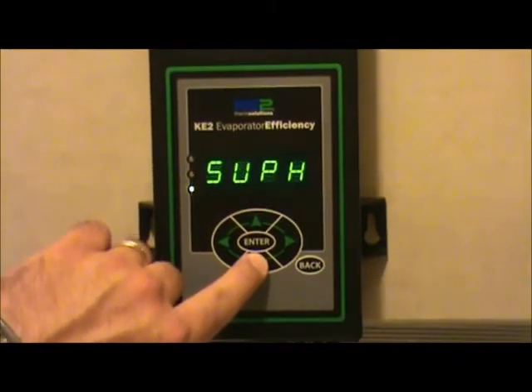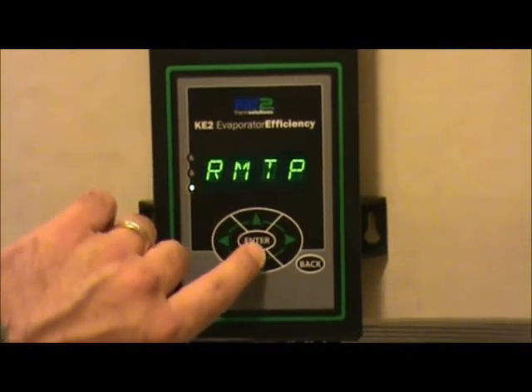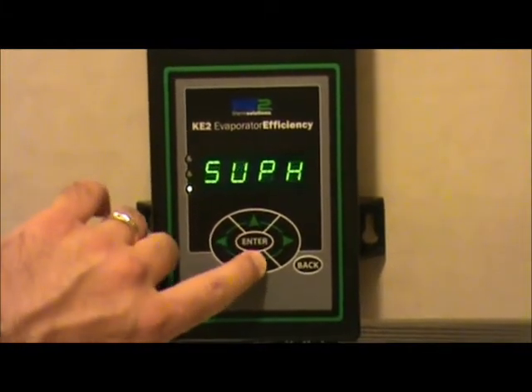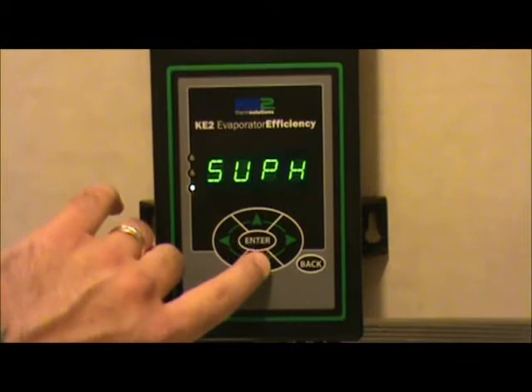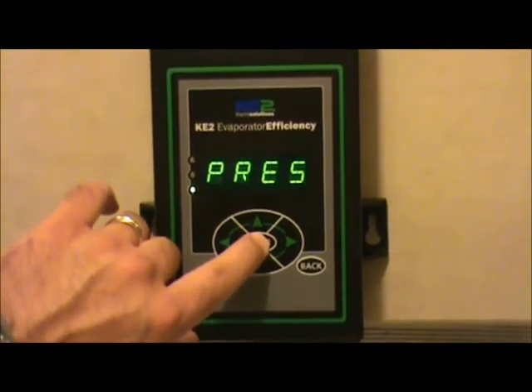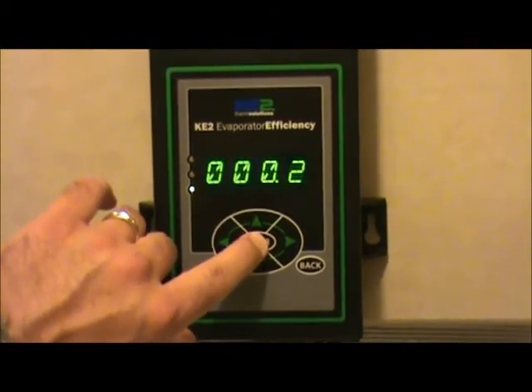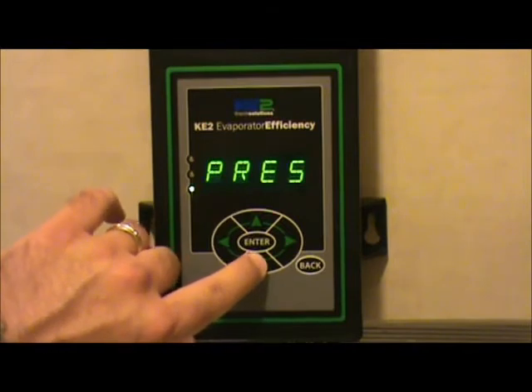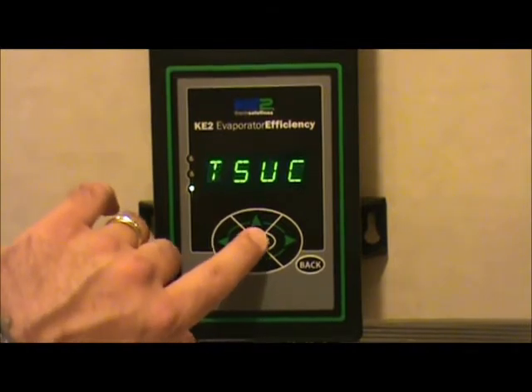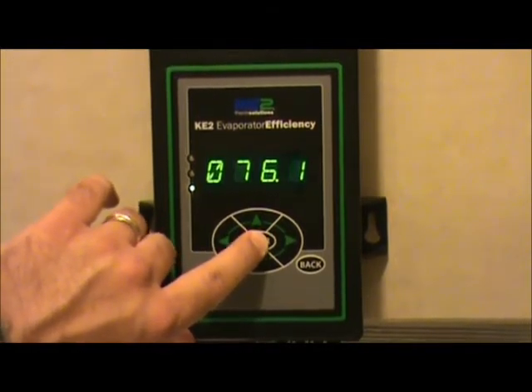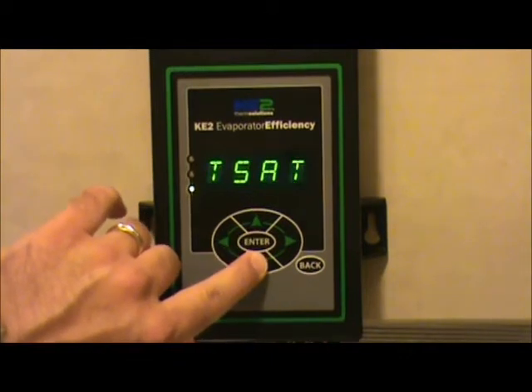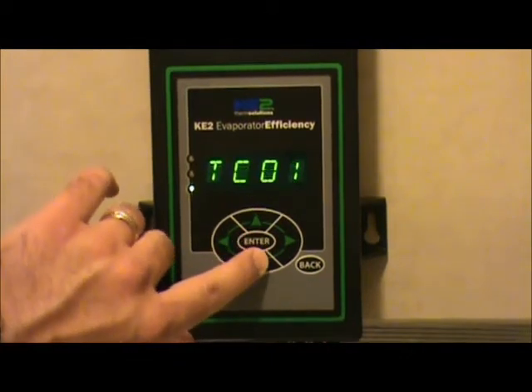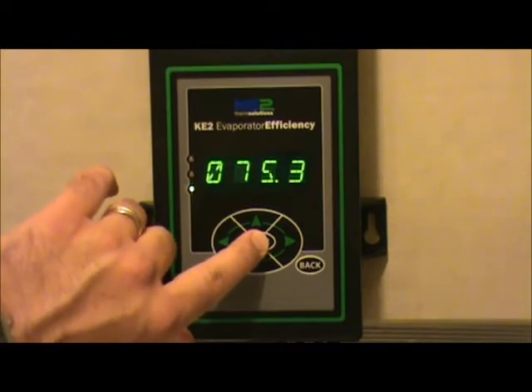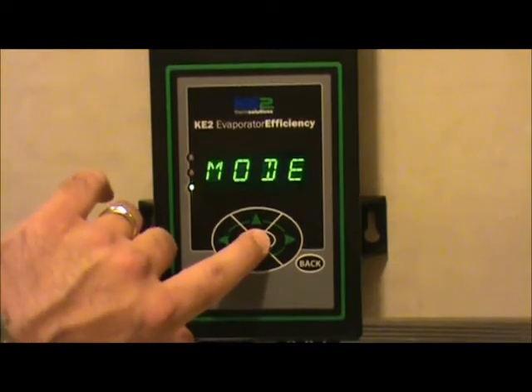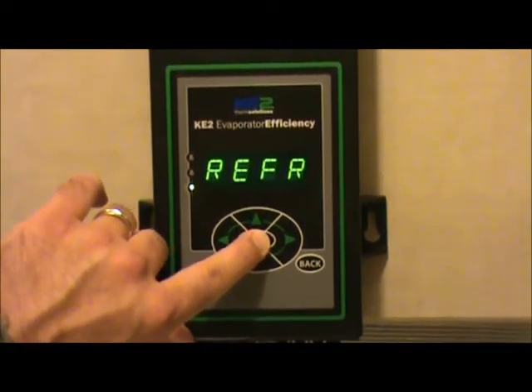There is a variety of things you can look at, including the room temperature, superheat, pressure transducer readout if you have one connected, temperature of the suction line if that's attached, the coil temperature sensor reading, and the mode the controller is in, in this case the refrigeration mode.